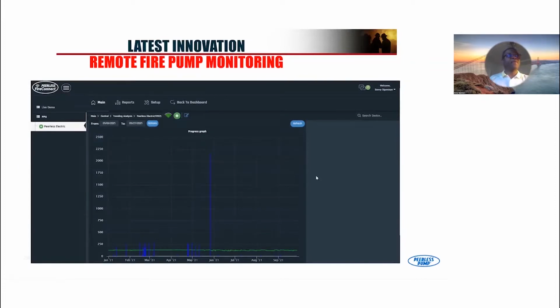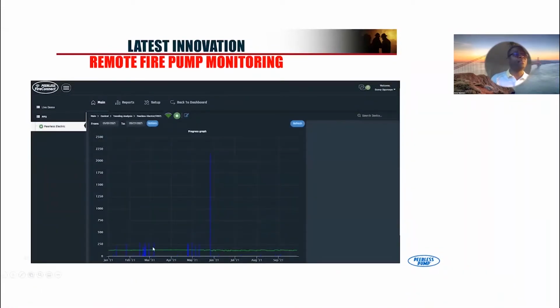And what I've also done here, I looked at the last 9 months on this particular sequence. You can see that everything looks normal. On this particular data, something happened and you're flowing a lot of water. You can see all these blue things are the flow going through the system, and on this particular day, something happened. It may well be somebody accidentally opened the hose valve and was using that to wet their lawns or something like that. But the pump wouldn't know any different, because when you open a hose valve, it thinks there's a fire. The pressure drops in the system and the jockey pump can't cope. Then the main fire pump opens up. So you can really see that.